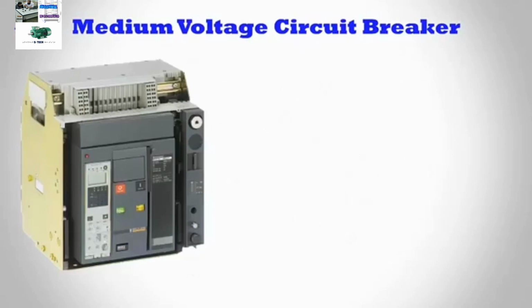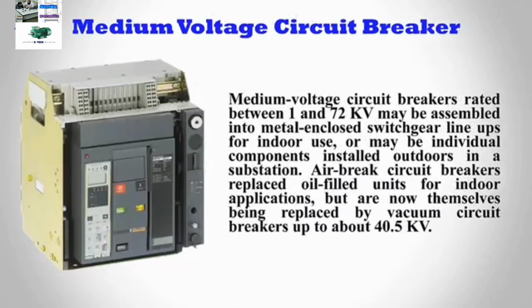Medium voltage circuit breakers rated between 1 and 72 kV may be assembled into metal enclosed switchgear line ups for indoor use, or may be individual components installed outdoors in a substation. Air break circuit breakers replaced oil-filled units for indoor applications, but are now themselves being replaced by vacuum circuit breakers up to about 40.5 kV.